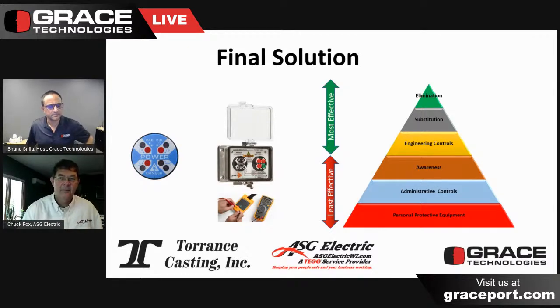When we looked at how Panduit presented its product, we don't really have this always-on indicator of voltage or immediate absence of it — at the end it just gives a green light saying go ahead and open the cabinet, without the opportunity for a qualified individual to intervene and test directly on the test ports of the voltage test system. But the additional safety protocol is: what is the line side of this cabinet doing? That voltage indicator on that side will be able to show us that voltage has indeed been removed from the line side of the enclosure as well.